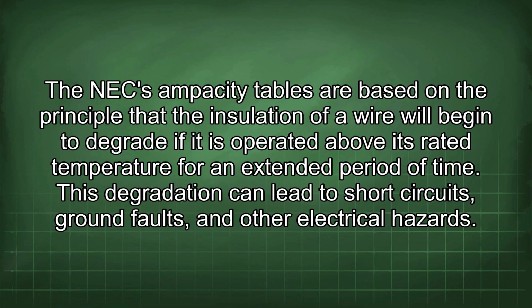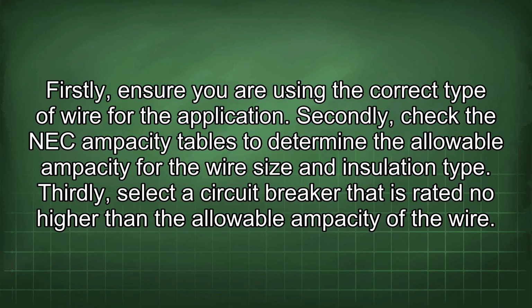The NEC ampacity tables are based on the principle that the insulation of a wire will begin to degrade if it is operated above its rated temperature for an extended period of time. This degradation can lead to short circuits, ground faults, and other electrical hazards. Firstly, ensure you are using the correct type of wire for the application. Secondly, check the NEC ampacity tables to determine the allowable ampacity for the wire size and insulation type. Thirdly, select a circuit breaker that is rated no higher than the allowable ampacity of the wire.